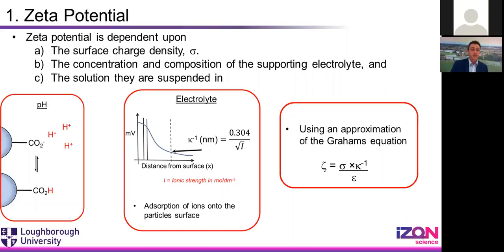So the zeta value that you measure is a function of pH, it's a function of ionic strength, and it's a function of the solution and liquid that you put it in, and the type of ions present. So when you give a zeta potential value, really what you should do is quote the pH, quote the solution, and quote the ionic strength that you've measured it in. For the same material, if you make a measurement of a zeta potential on a different instrument under a different set of conditions, you will get a different value.